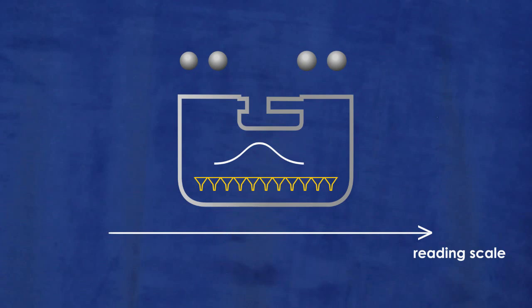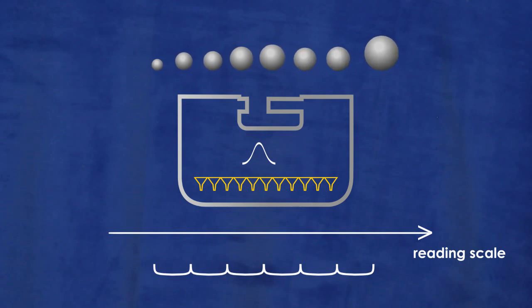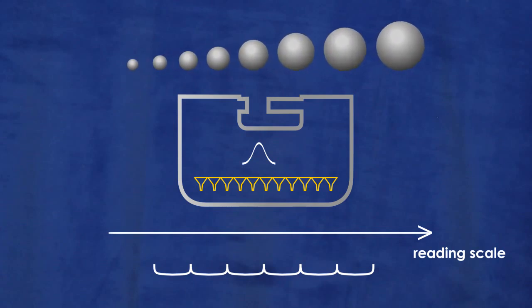This situation can be improved by lowering the repeatability error, but what if the gauge R&R is already adequate for the purpose of our measurement? Then the option is to increase the variation among the parts. The idea is that in order to estimate the gauge R&R with adequate quality, we need to make sure we have sufficiently different parts in the experiment. The NDC parameter is now not a measure of the quality of the measuring device, but a measure of the quality of our experiment.